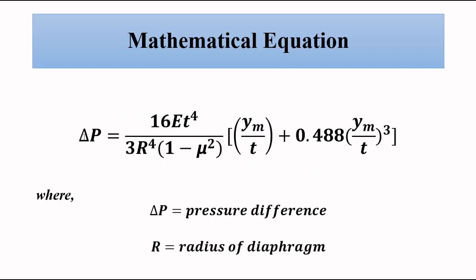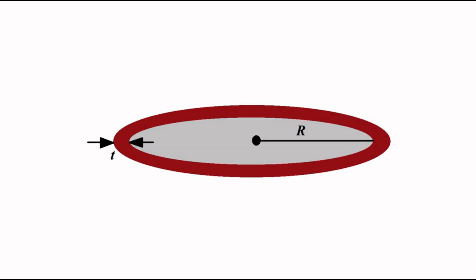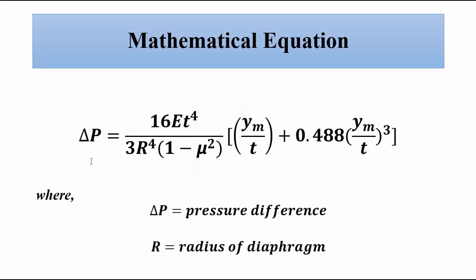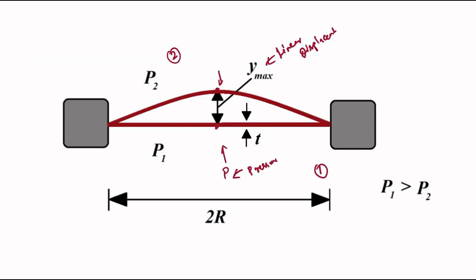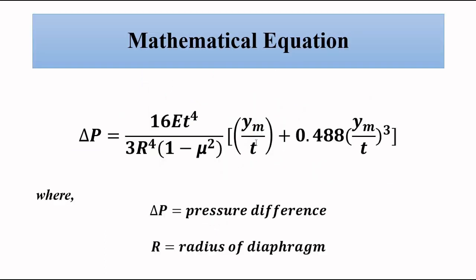Higher minus lower. So that pressure difference is equal to 16 E T to the power 4 by 3 R to the power 4 into (1 minus mu square), where E is Young's modulus of elasticity, T is the thickness of the thin plate diaphragm material, R is the radius of the diaphragm, and mu is the Poisson's ratio, into Ym, the maximum linear displacement, divided by the thickness, plus 0.488 times Ym cubed by T cubed. This is for the maximum condition. For a particular instantaneous displacement, we can simply put Y, that particular displacement. So this is the relationship.